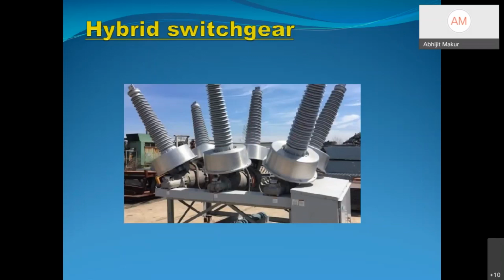A hybrid switchgear. Since the space requirement for an AIS substation is very large, and that is not available at present, we have gradually shifted from AIS substations to hybrid switchgear, wherein the isolator, CTs as well as the switchgear are in one capsule. We require much less space than with normal conventional switchgear. And wherever in old substations we need to extend the number of bays because of increased load demand, this is the most preferred form used by utilities at present.